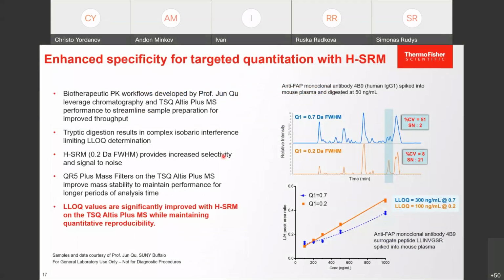And the last part of improved productivity, I want to mention that a highly selective SRM means that we can take the full potential of our TSQ platform, and we can use a narrow quadrupole isolation window, not 0.7 but 0.2 on the TSQ Altis instrument. And what does it mean? That with a narrow quadrupole window, we can filter out lots of matrix interferences, which means that we can filter out lots of matrix noise.